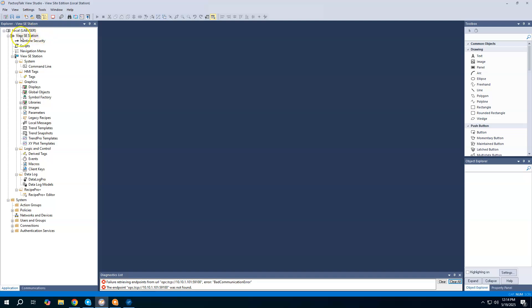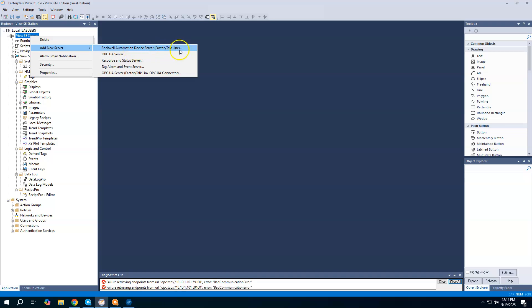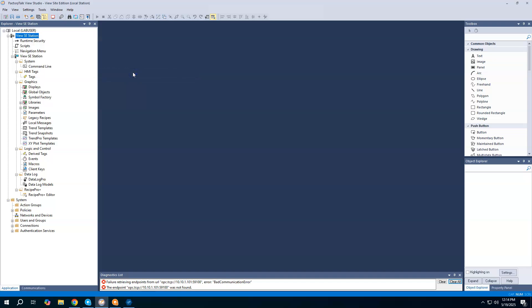To use the OPC UA connector, we're going to come up here to the project name. The project is called View SE Station. I'm going to right-click and say add a new server, and we're going to say OPC UA server, which is going to be the FactoryTalk Linx OPC UA connector. Note our other options here is we can create a device server for Rockwell devices, that's a FactoryTalk Linx connection. We could set up an OPC DA server. But we want to use the OPC UA server because that's what Optics is using. Optics is an OPC UA server.